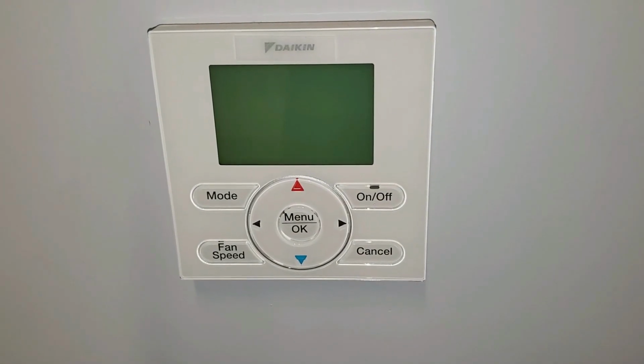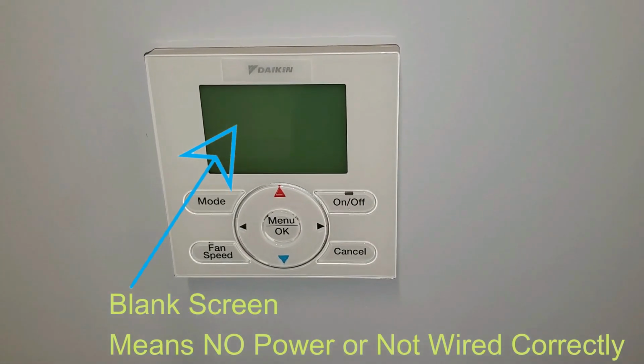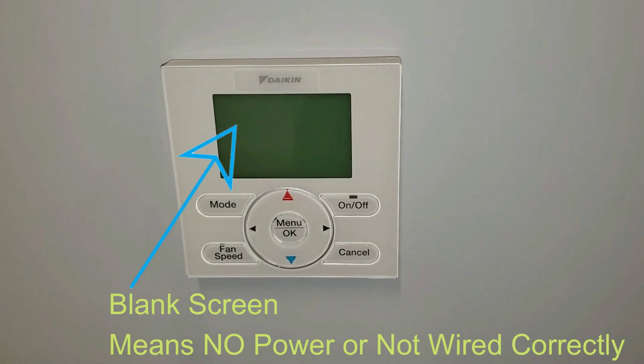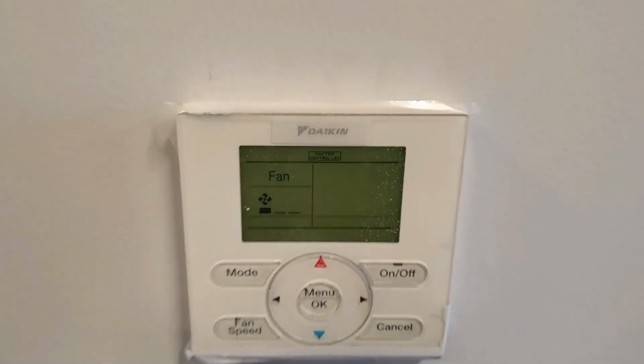So in step 1, you want to power up all of your indoor equipment. You're going to then walk the job site and look at all the thermostats because you want to make sure that all the indoor units actually have power. And the way that you can do this very easily is by looking at the thermostat. If the thermostat has a display, there is power being supplied to that thermostat from the indoor unit. Now, that doesn't confirm that the system is wired properly, but it does confirm at least we have power. But when I say go check all of the thermostats for a display, I mean go physically verify that every single thermostat has a display.